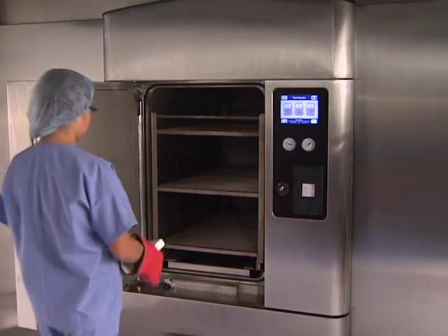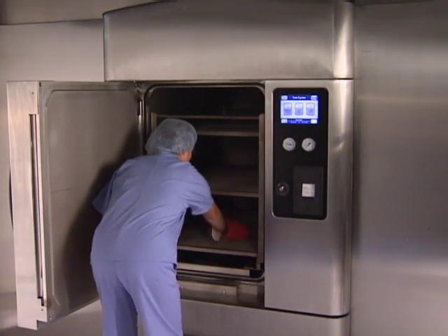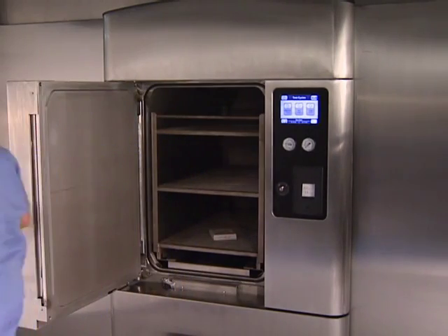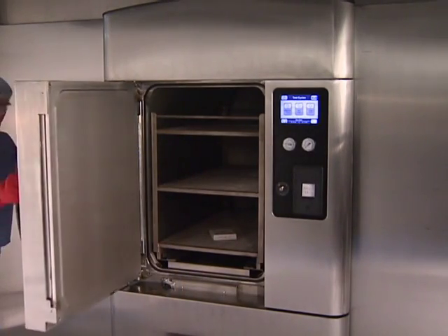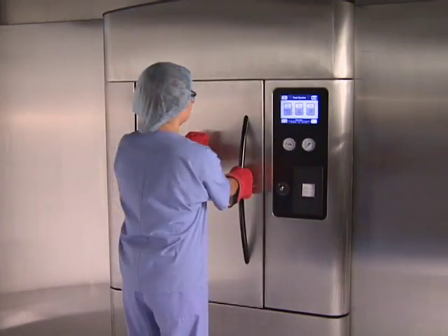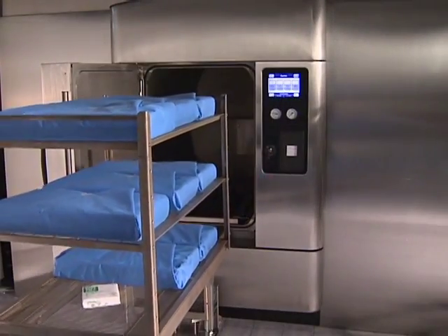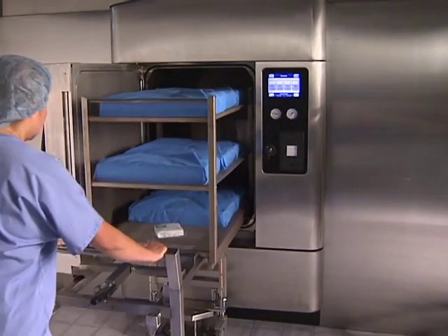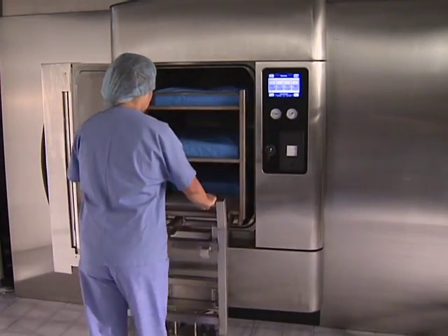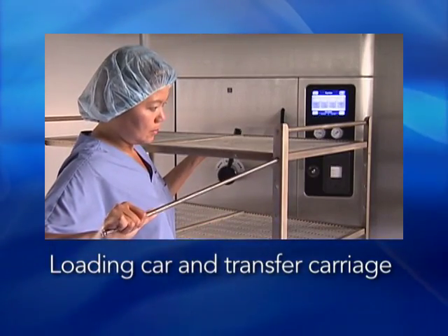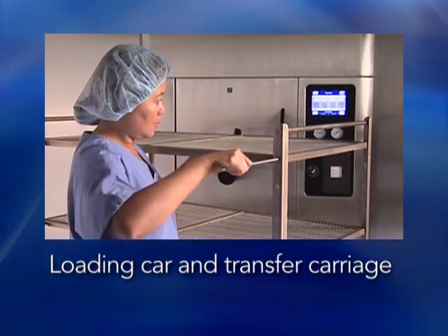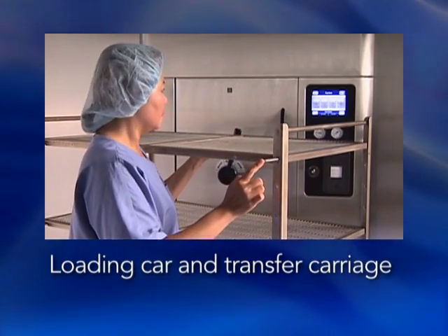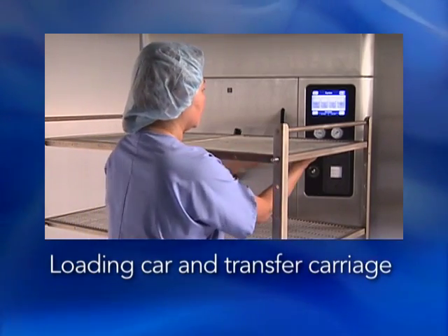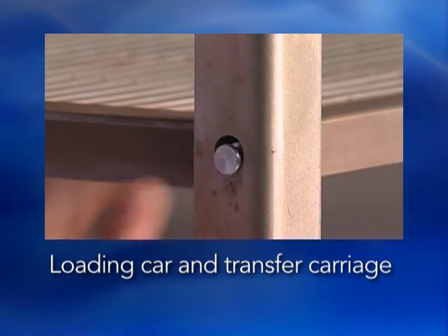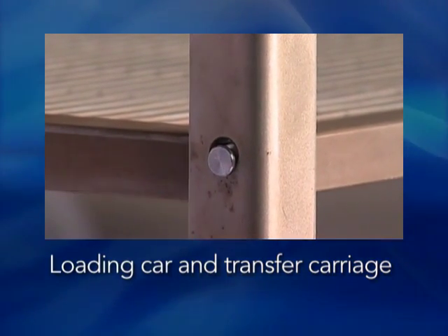If it's the first cycle of the day and pre-vacuum cycles are being used, you'll also need to run a DART or Bowie Dick test before processing a load. We'll review this procedure in the next segment. Use the loading car and transfer carriage to place the load to be processed into the sterilizer. Each loading car comes standard with either 1 or 2 adjustable stainless steel shelves and 1 fixed shelf. An additional optional shelf may be used to maximize throughput. Shelf height can be adjusted without tools.